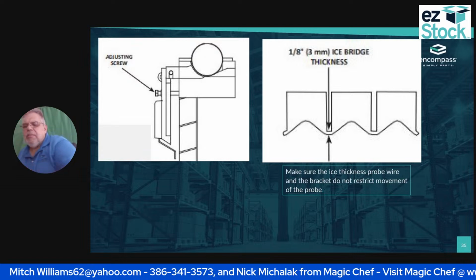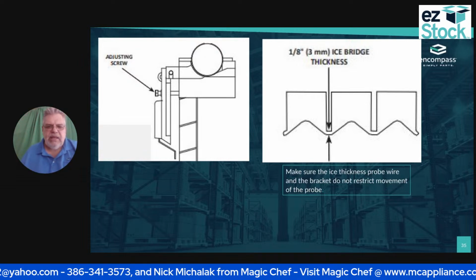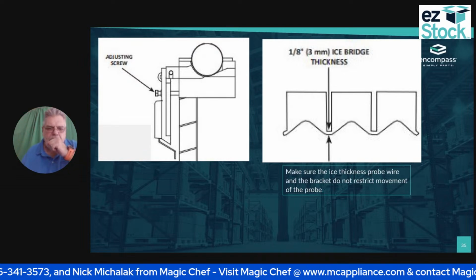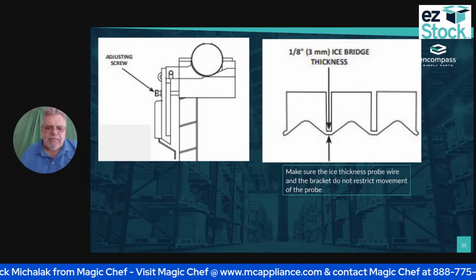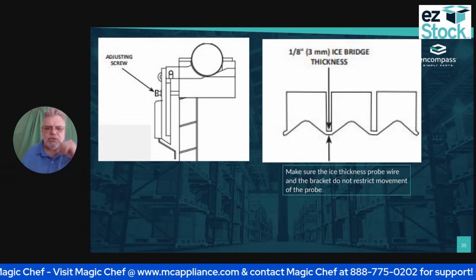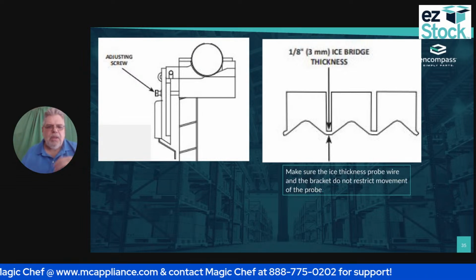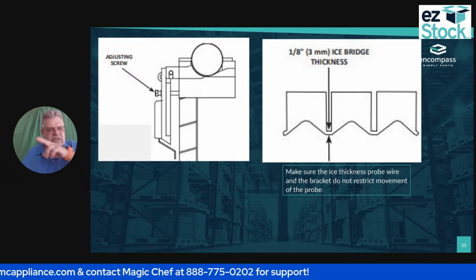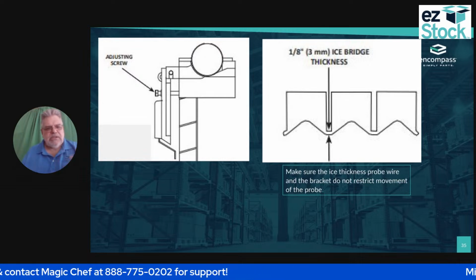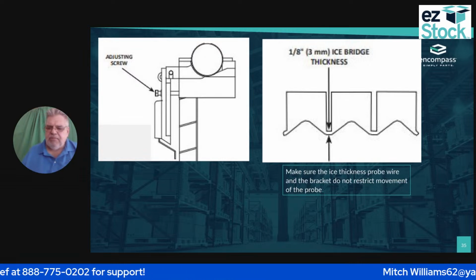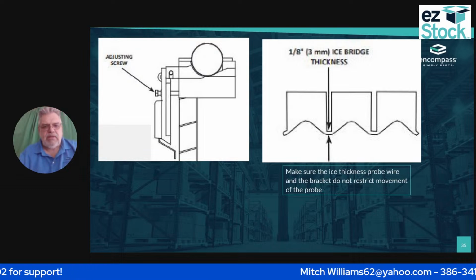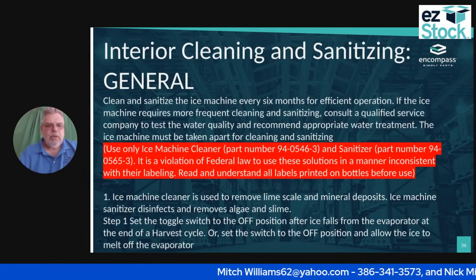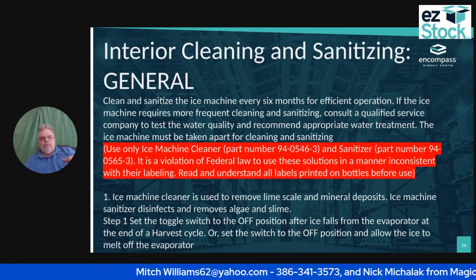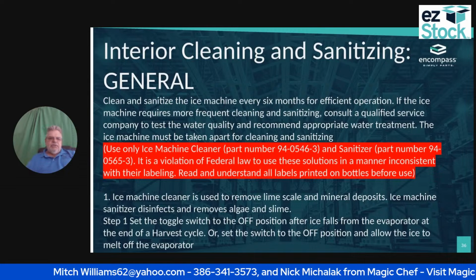The one thing you have to be really careful about is that the ice thickness probe wire and the bracket do not restrict the movement of the probe. So I have to make sure that it is freely movable, because if it's not, I'm never going to get the right thickness. Okay. Now we're going to go through the general cleaning procedure.